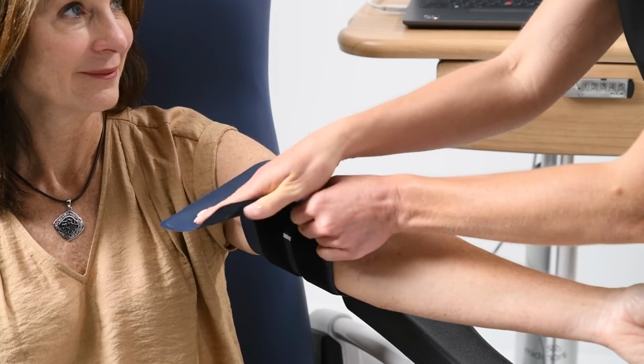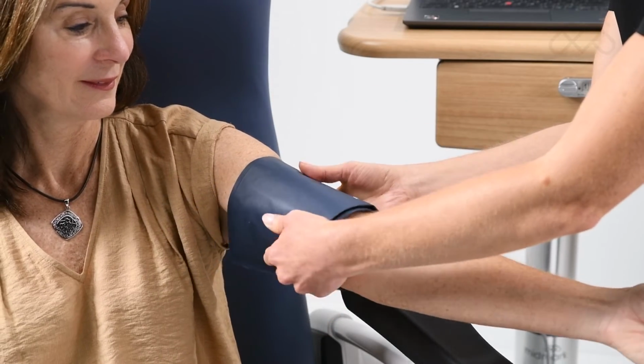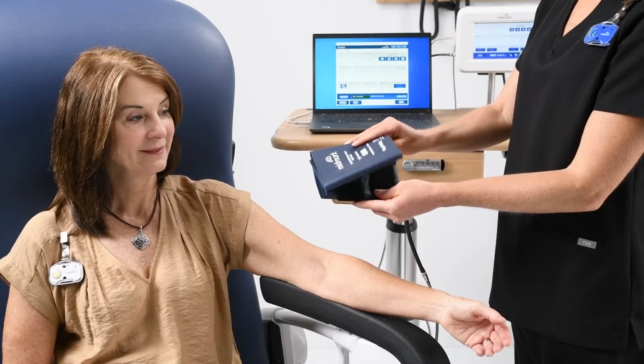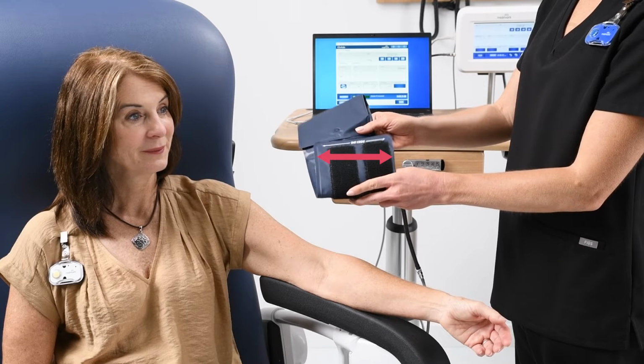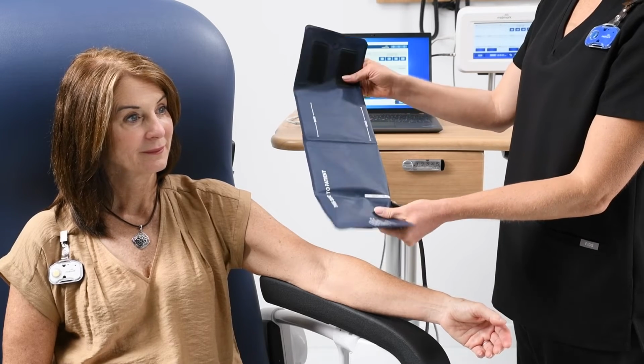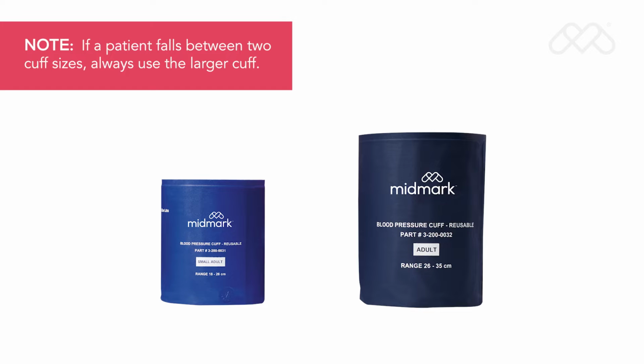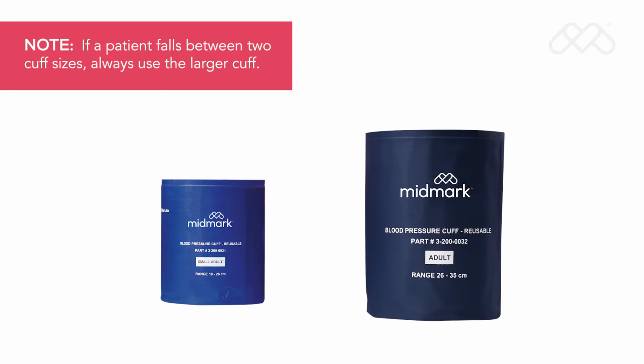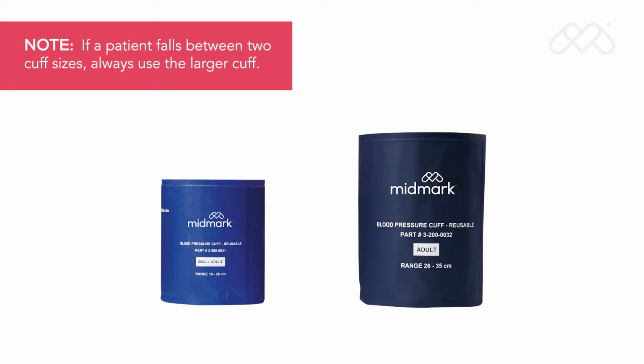To verify the proper cuff size for a patient, wrap the cuff around the patient's extremity. The index line, or white arrow, should fall within the white range markings on the cuff. If a patient falls between 2 cuff sizes, always use the larger cuff.